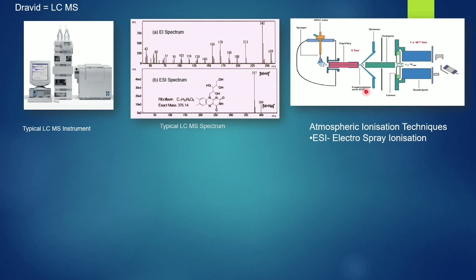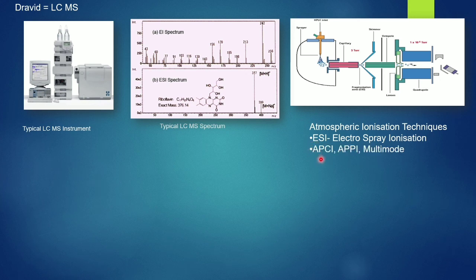We have multiple techniques available. One is called ESI — electrospray ionization. The reason it is called electrospray ionization is that you put a nebulizer gas which sprays the liquid coming from the HPLC column in the form of a spray, and then you apply an electric charge. Then we have atmospheric pressure chemical ionization — APCI. In APCI, if your molecules are more non-polar in nature and cannot take the charge directly from your capillary tube...